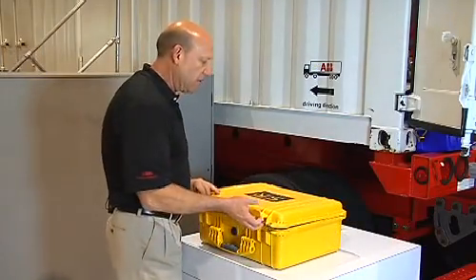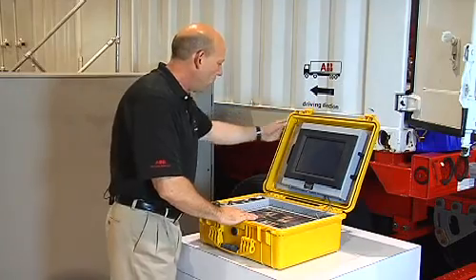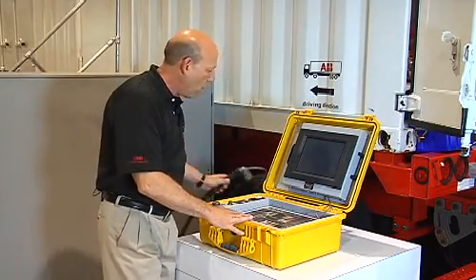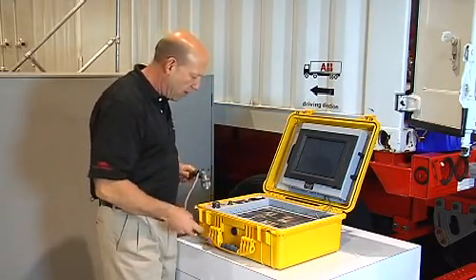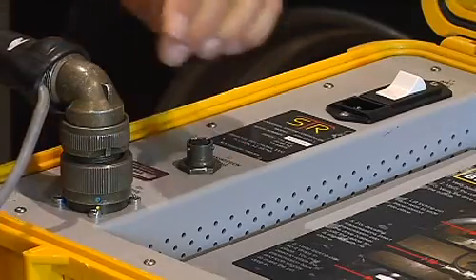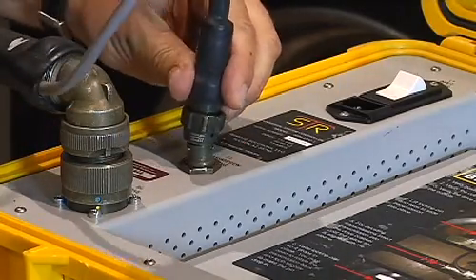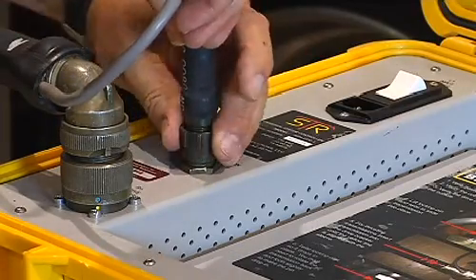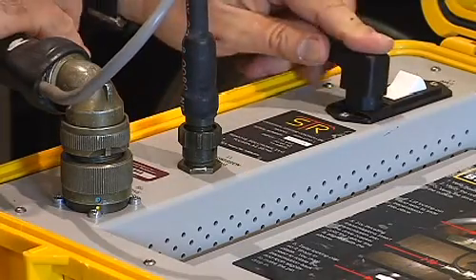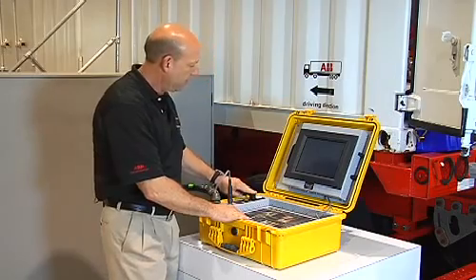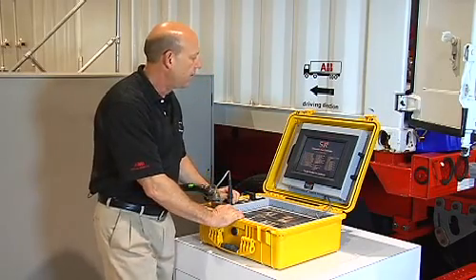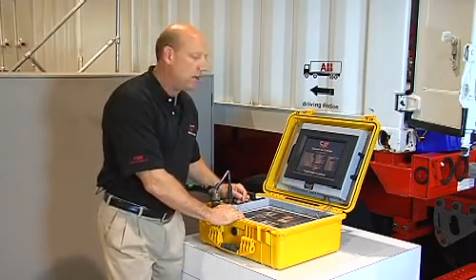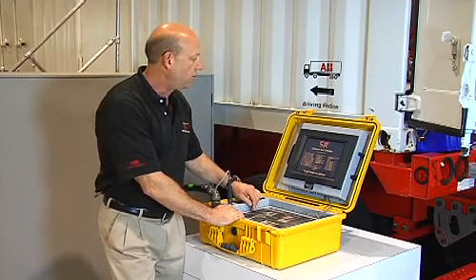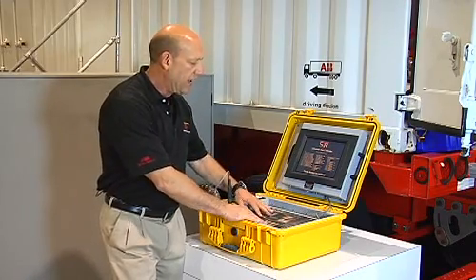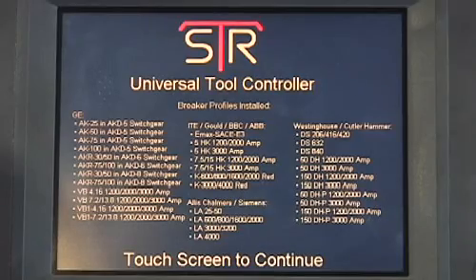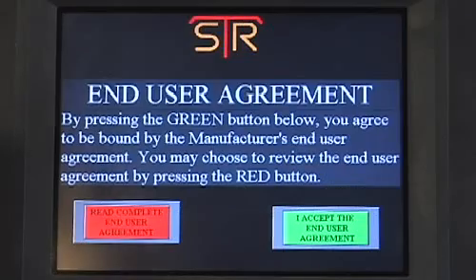Now we'll set up the system controller, setting it up about 30 feet away from the work to be performed. Take the other end of the power comm cable, connect it, transmission connection, take the power cable for the system controller, plug it in, turn on. We will get our greeting screen, which is the breaker profiles installed, letting us know what applications may already be resident in the system controller. We'll just touch the screen to continue.